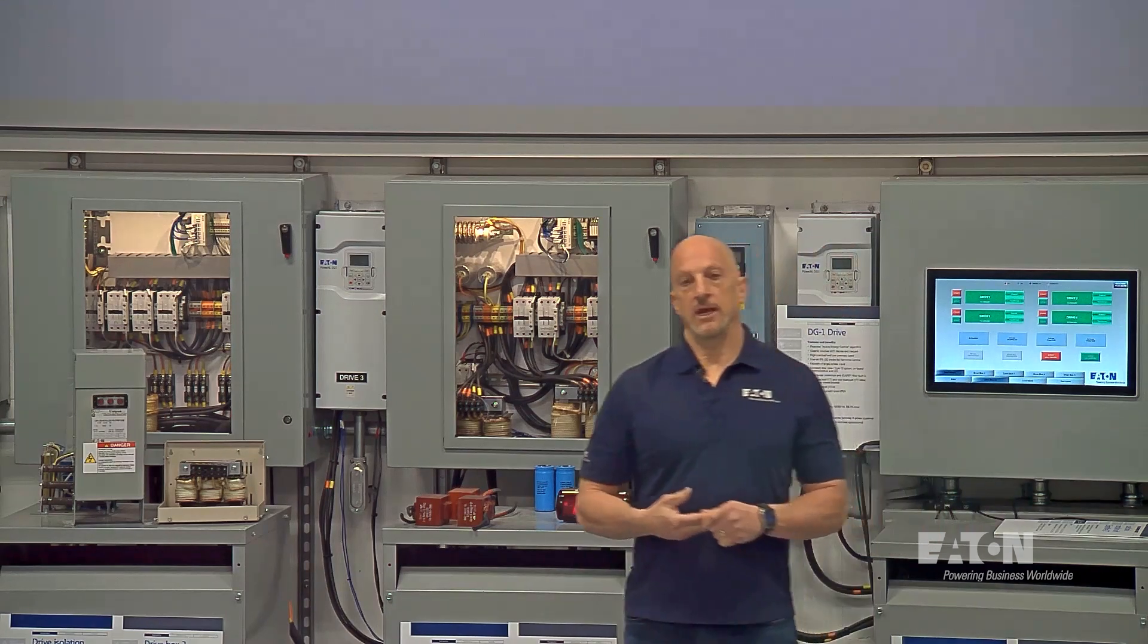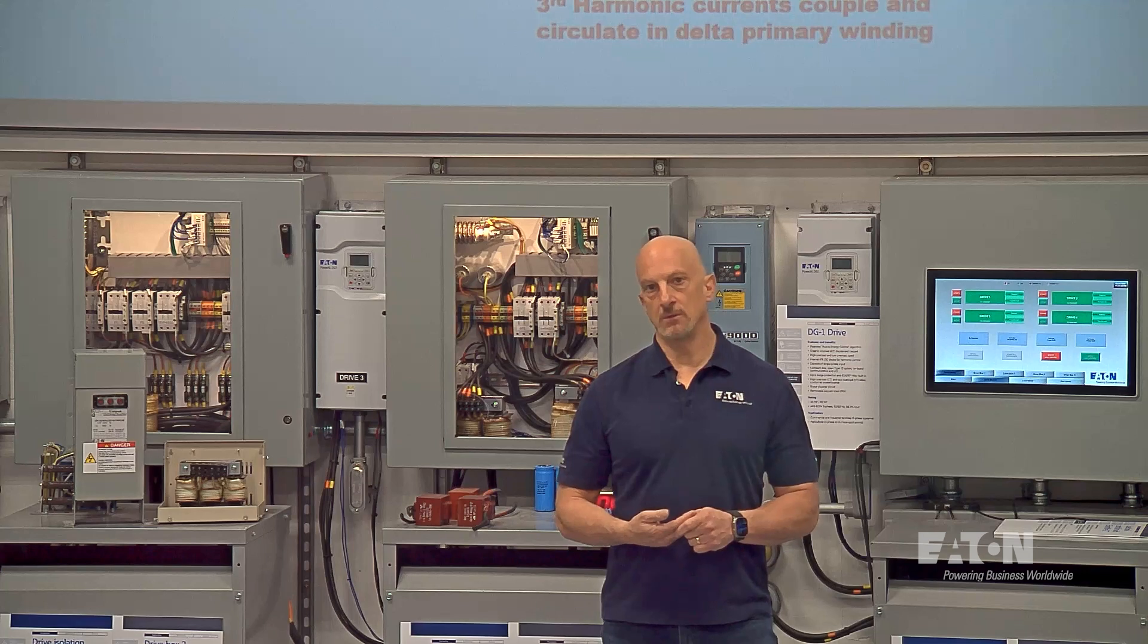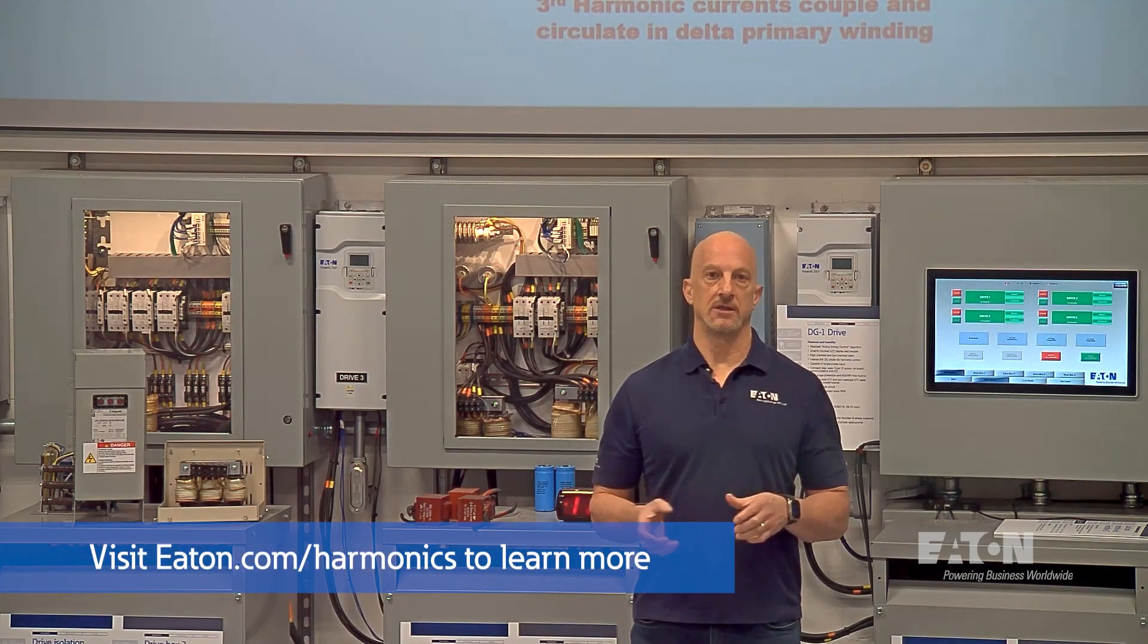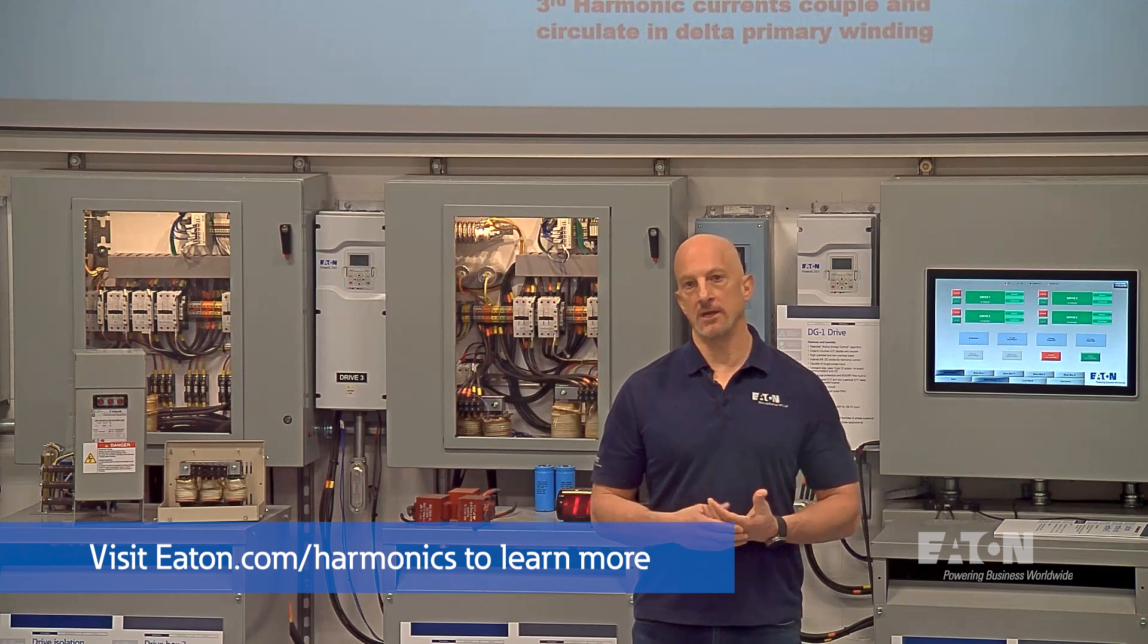So to answer the question, if we had more than 100% distortion on the neutral, it's not a concern unless the current itself is higher than the rating of the neutral.